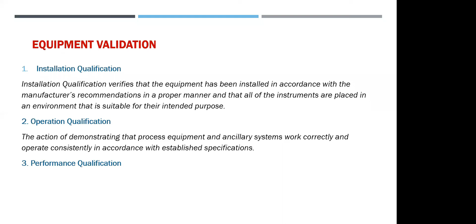Brief definition of IQ: it verifies that the equipment has been installed in accordance with the manufacturer's recommendations in a proper manner, and that all of the instruments are placed in an environment that is suitable for their intended purpose. Operation qualification: the action of demonstrating that process equipment and ancillary systems work correctly and operate consistently in accordance with established specifications. And then performance qualification: assurance that the process continues to comply with established requirements and consistently performs as intended for the selected application.